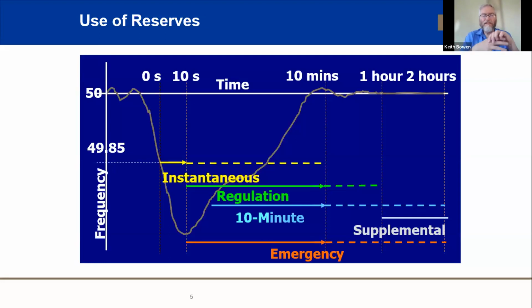Diesel, once it's running, or a gas plant when it's running, can provide regulating reserve and theoretically would be able to provide instantaneous reserve while running, same as a coal plant. But usually we don't have the diesel running 24 hours - sometimes, but we try not to. So generally, instantaneous reserve tends to be limited to the coal power stations, since they've got the governors to allow us to do that.